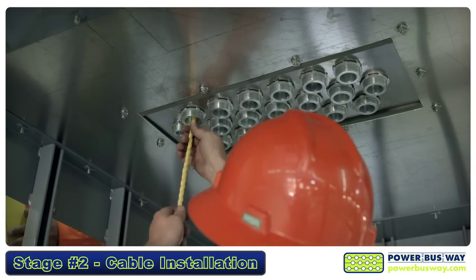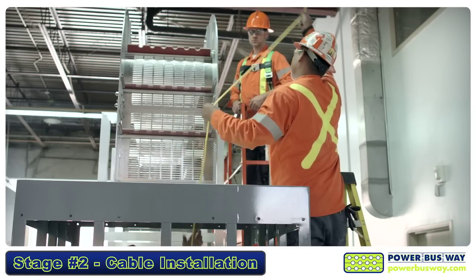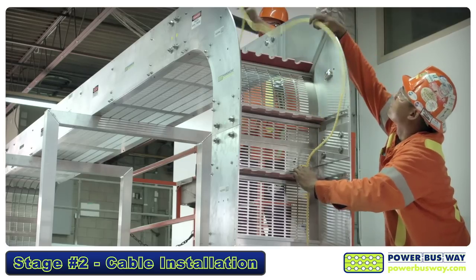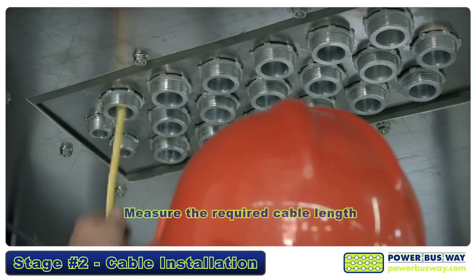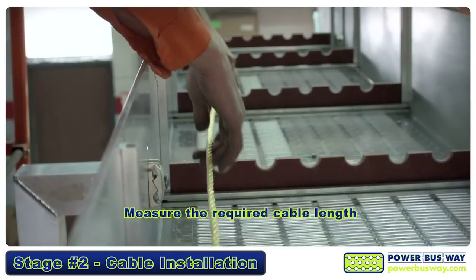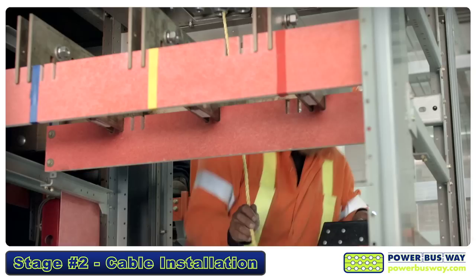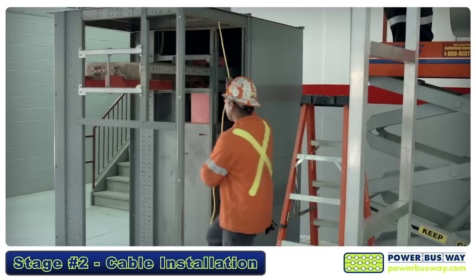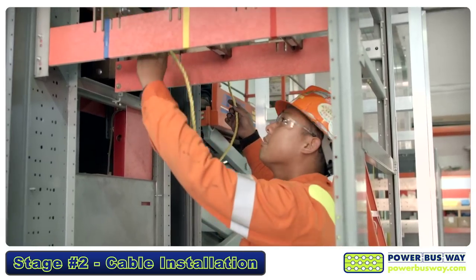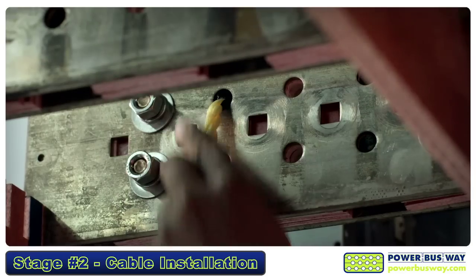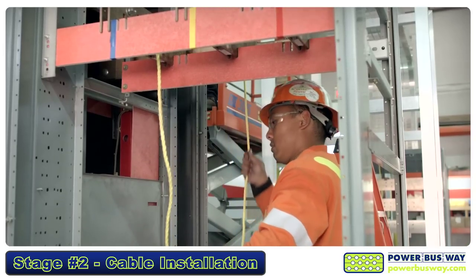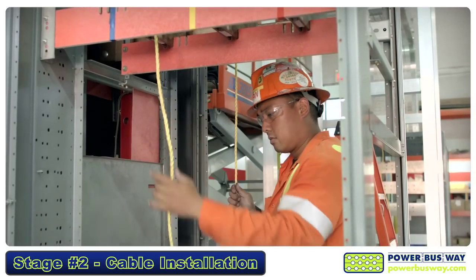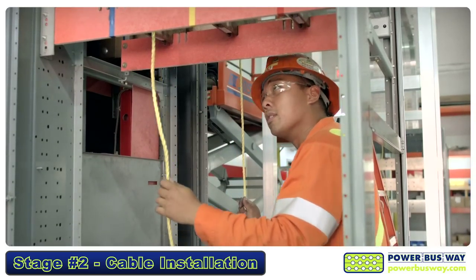Using any standard rope, you'll be able to confirm the proper cable lengths as shown on the bill of materials. Thread the rope through the equipment entry flange and guide along the cable bus enclosure to reach the termination compartment. Allow enough slack on each end to ensure the cables will land properly on each bus bar. Always remember to use the path of the longest possible length and ensure all phase cables are equal in length.